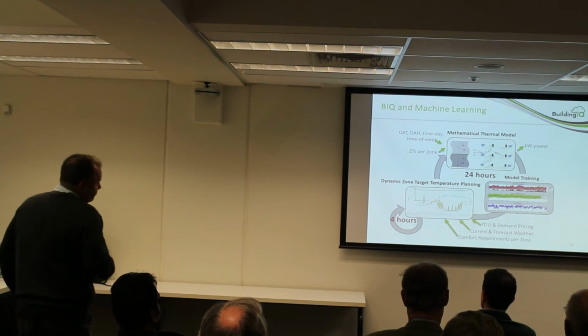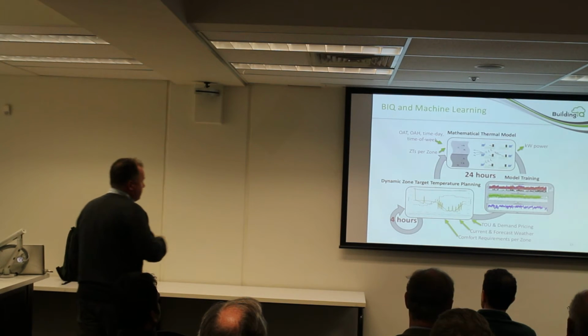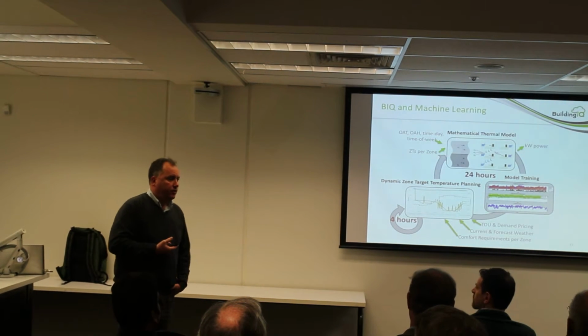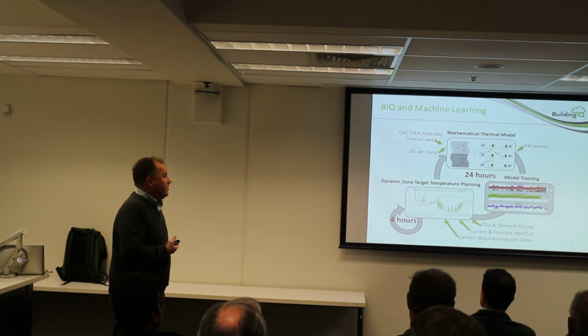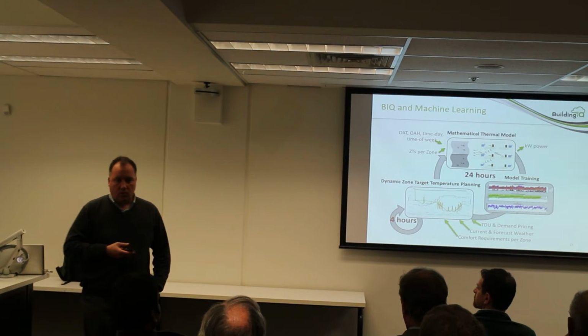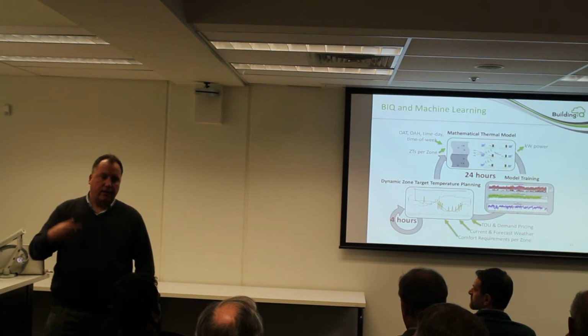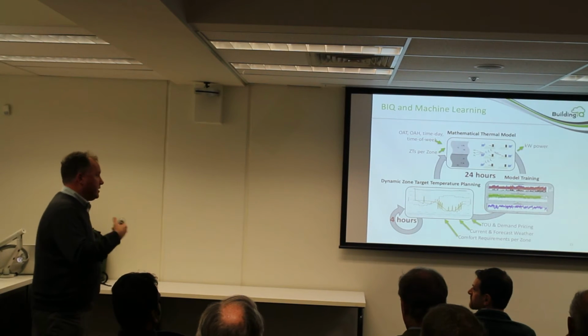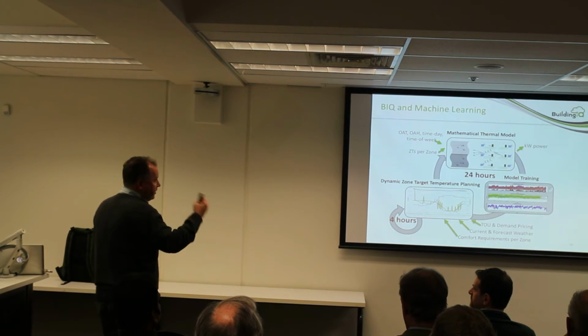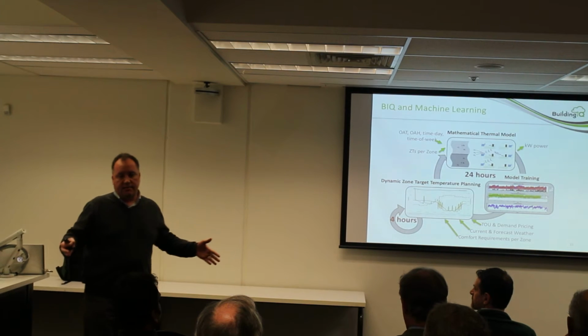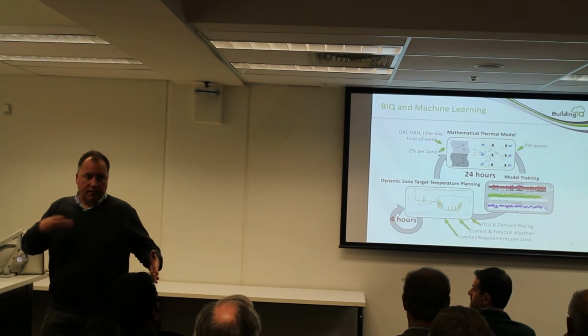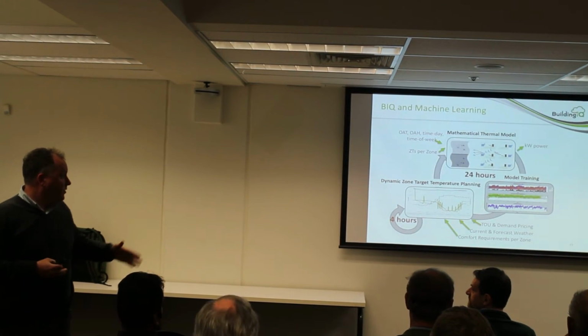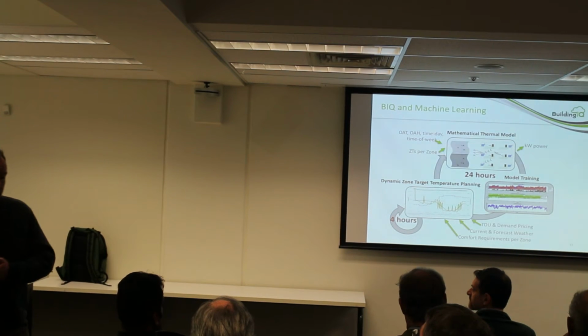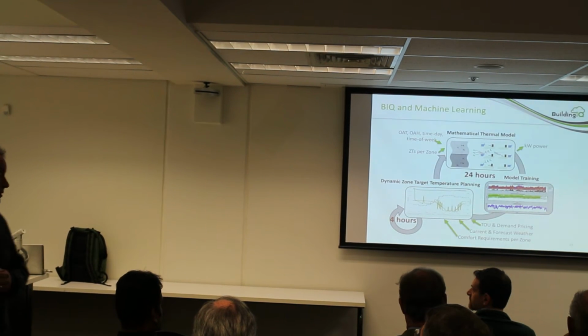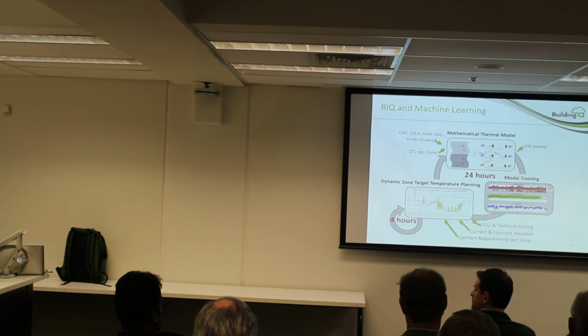That's essentially how we go from the high level down to the low-level zone controls of the building. The machine learning part of Building IQ is this constant learning that the model is doing. Every night it recalculates based on the current data set. We take 90 days of data. It calculates a new model, a new power prediction comes, and then we're able to start producing predicted targets for the next day.